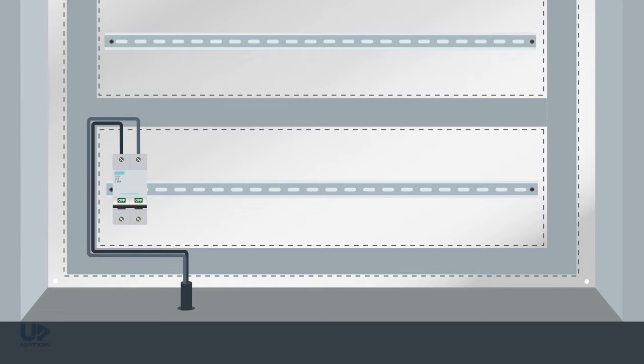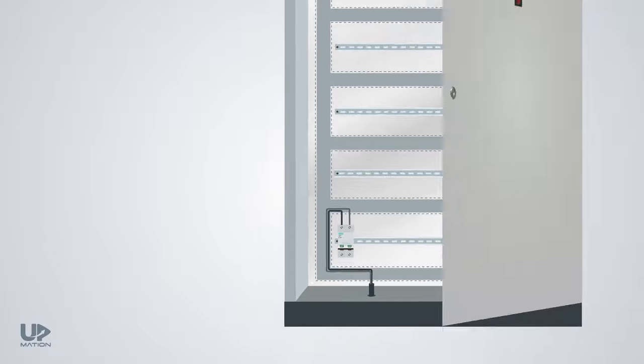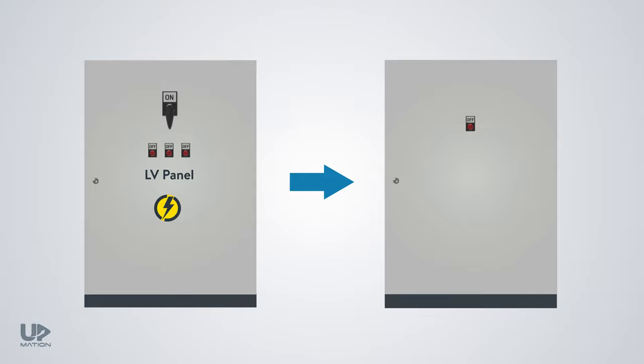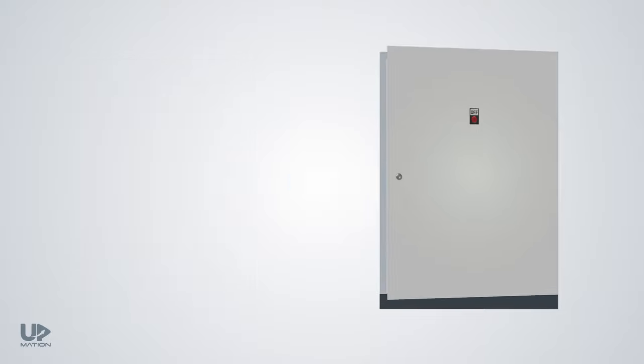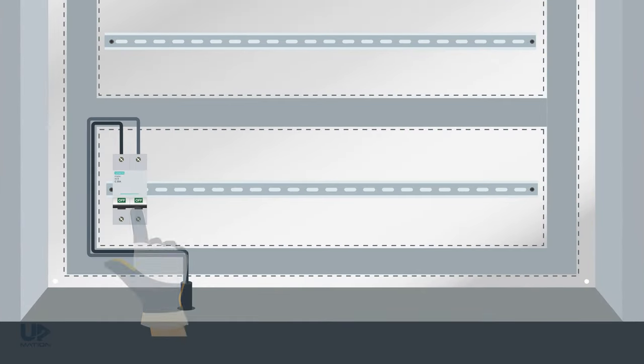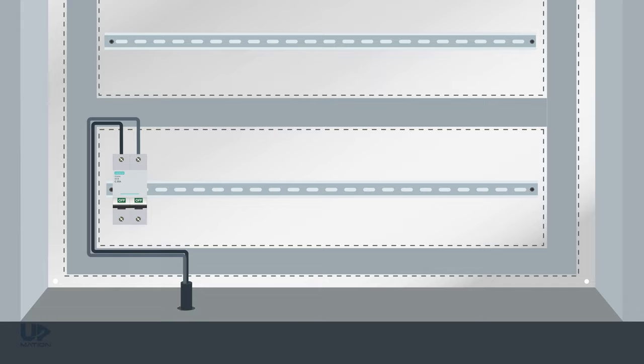This electric power comes from another panel within the electrical room, like a kind of low voltage power distribution panel. Either way, the MCBs are a type of protection circuit breaker that are used in the entrance of the panels with different consumptions up to 25 amps. They protect our panel from overload and short circuit faults. Furthermore, we can connect and disconnect the whole power to the panel manually using this MCB.